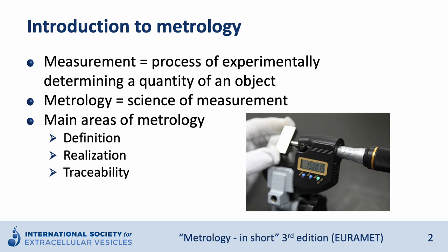Let me give you an example. Gauge blocks are used to calibrate micrometer screws. These gauge blocks are small metal pieces with calibrated dimensions. This calibration is performed by optical interferometry, which uses lasers. This provides the connection to the definition of meter, because meter is defined based on the speed of light, and that is realized at the primary level in terms of the wavelengths of an iodine-stabilized helium-neon laser.